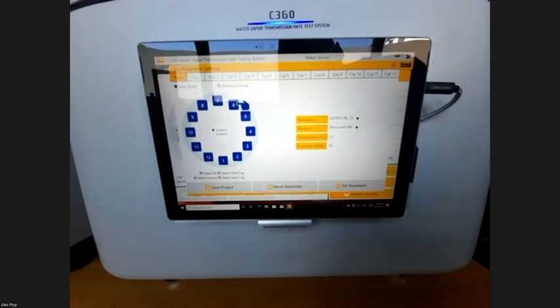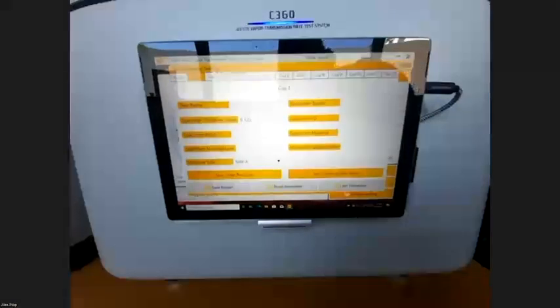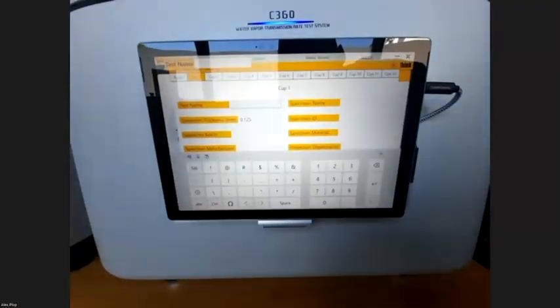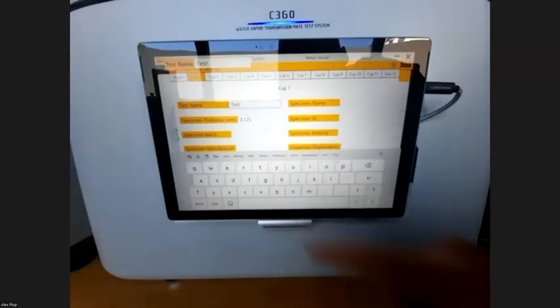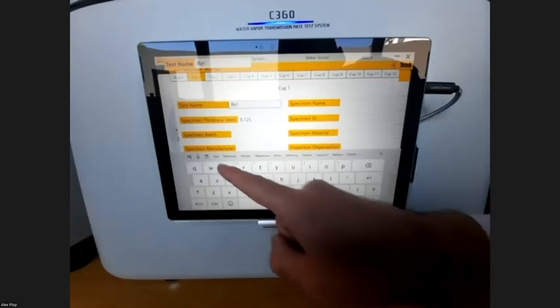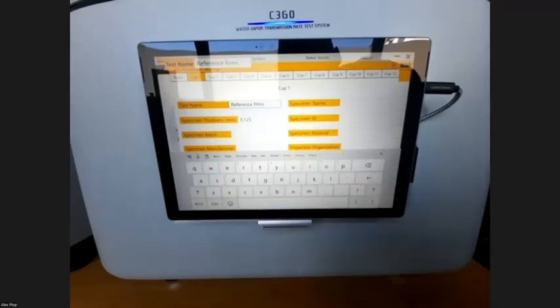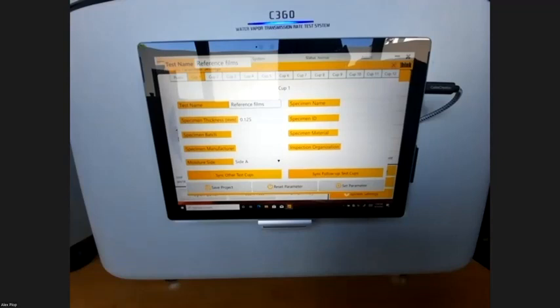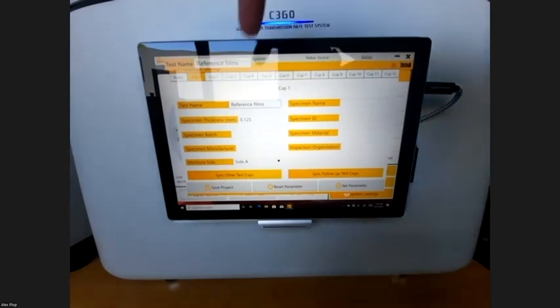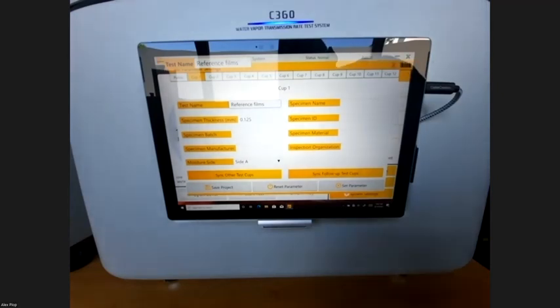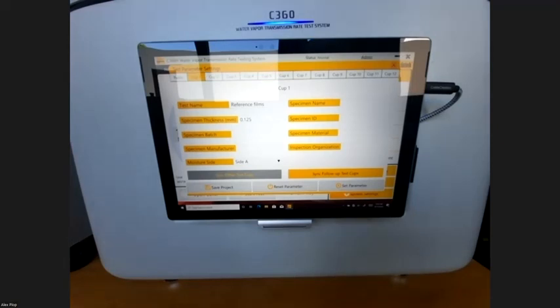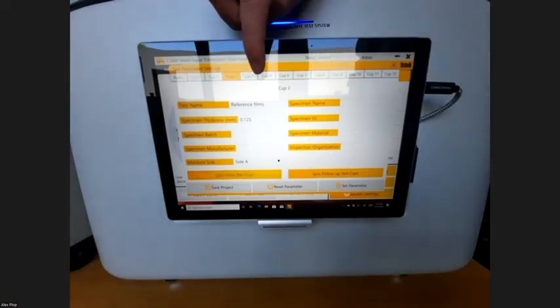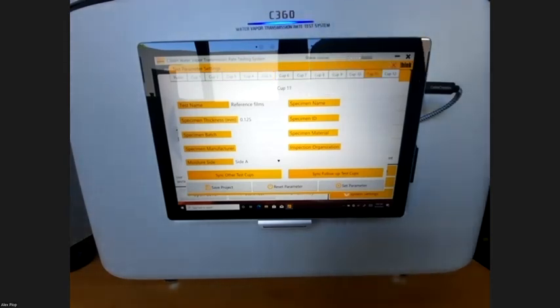Now, this would be the main parameters of all the cups, but also if I select cup number 1, here I have the freedom to input all the information that I want regarding my test. So here, all the spaces can be modified and filled up by the operator. For example, if we use the same type of material, the same sample in all the cups, you don't need to go to all the cups to input the information. You just input it for one, like I did, and I will just press sync other test cups. This means that all the information that I have filled in cup 1, I can easily see for all the cups that I have here.